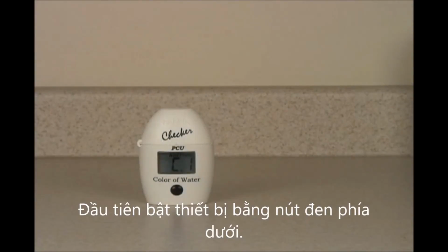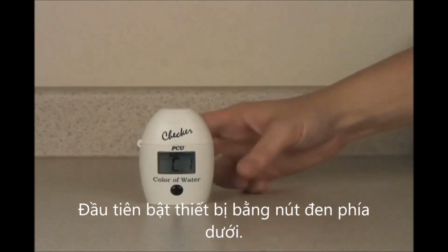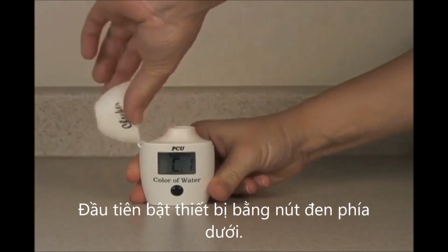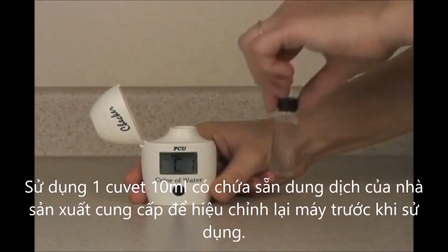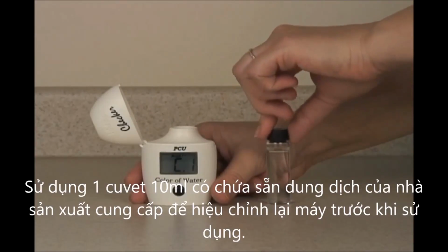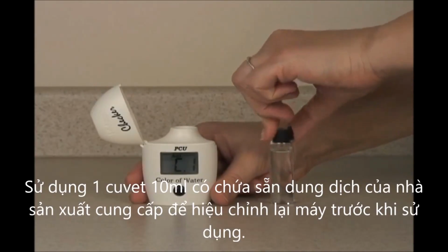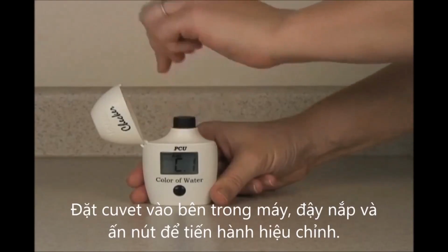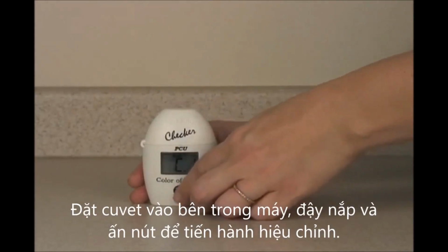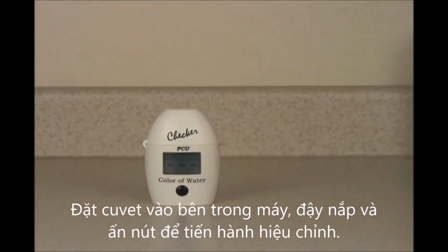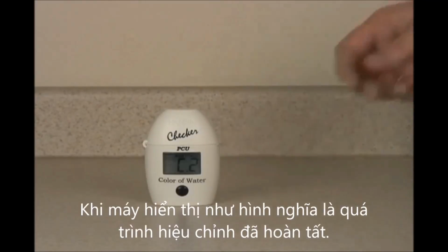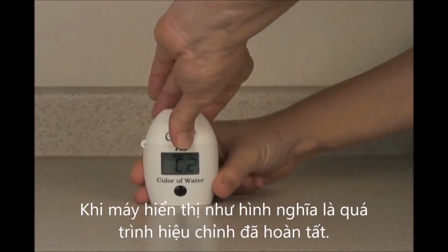Today we're going to test the color of water with the HI727 color of water checker. The first thing you do is zero the instrument. So you fill a vial with 10 milliliters of deionized water. This is your blank. Put the blank in the checker and press the button once to zero it. When the meter says C2, you're ready to measure the apparent color.